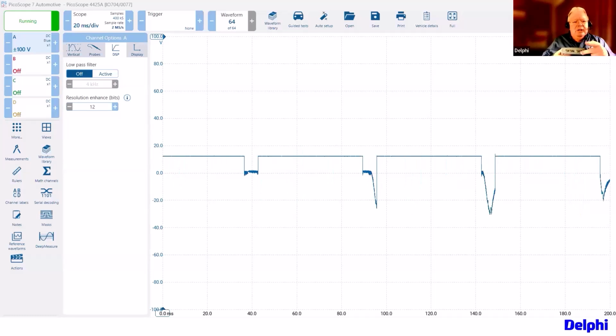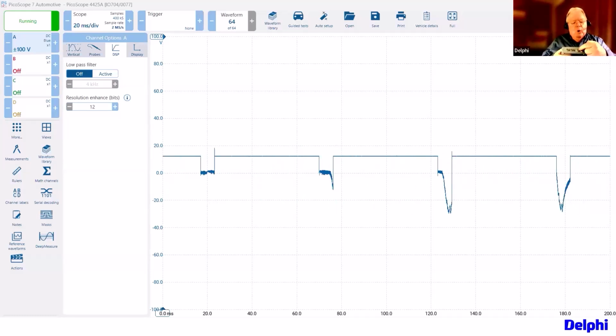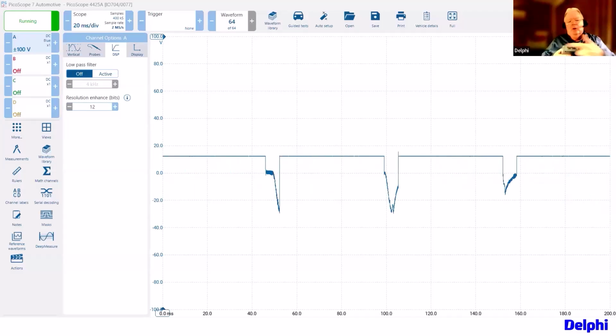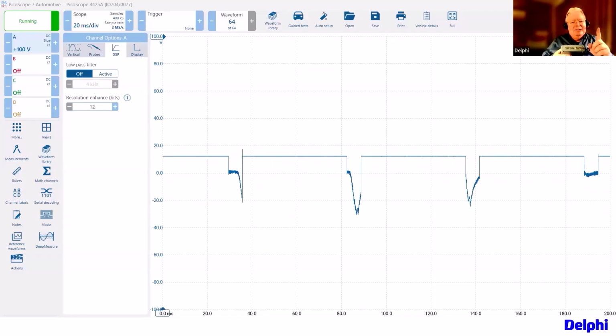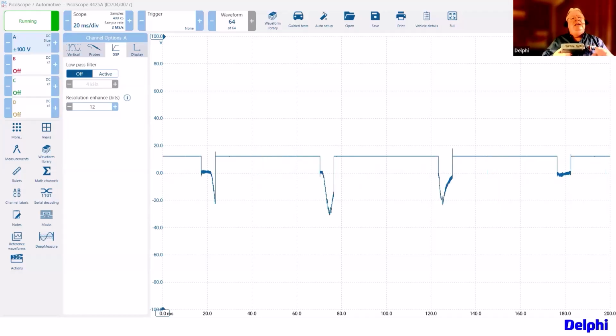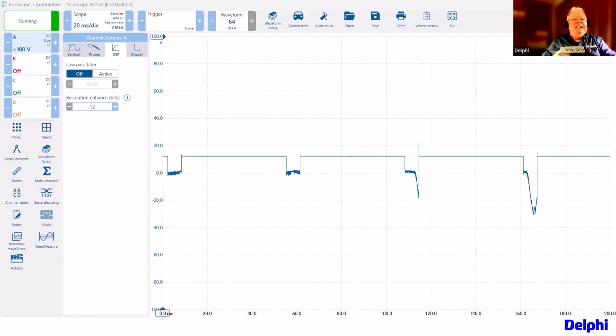This is where I killed this. The attenuator wasn't a problem, I used one. When you only need one ground for all 4 channels, or 2 channels, or 8 channels, that's a common ground. And when you have a common ground, that's an issue when you're dealing with AC line power, like power from the wall socket. And as we get into EVSE, electric vehicle supply equipment, that's the level 1 and level 2 charge cables for plug-in hybrids and EVs.